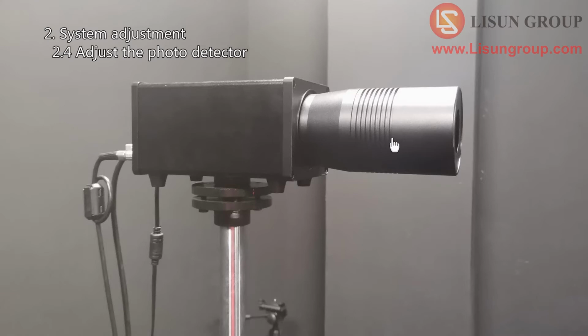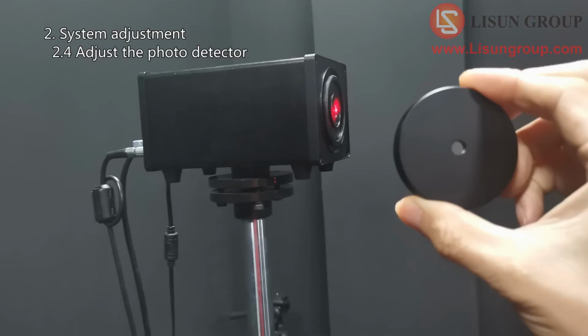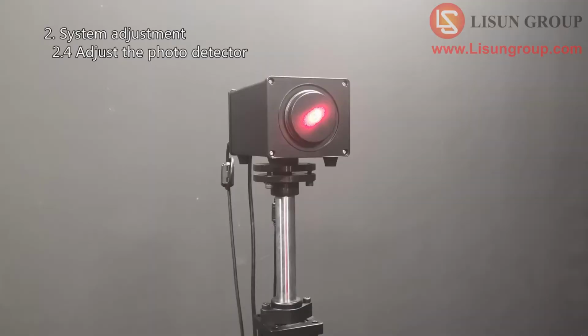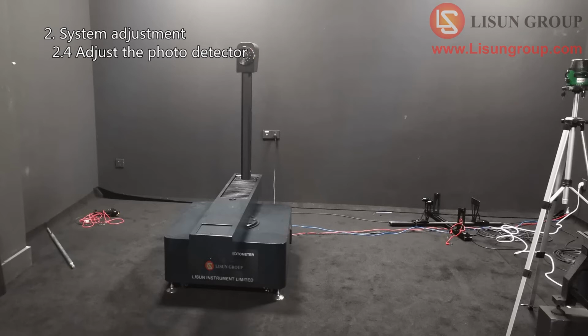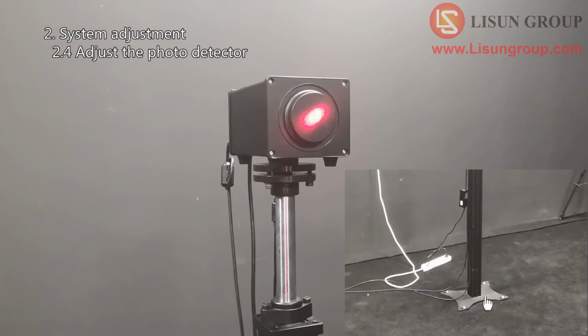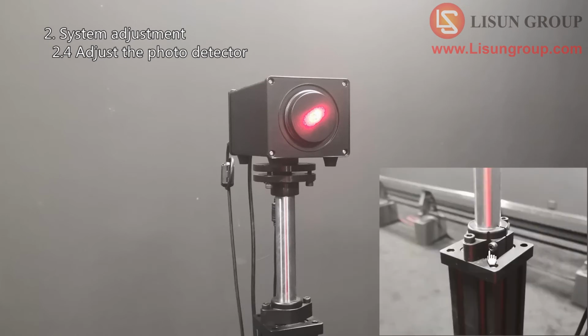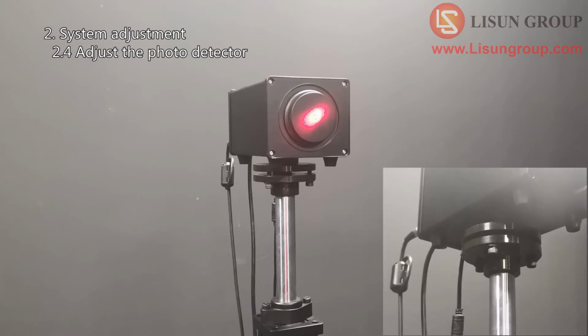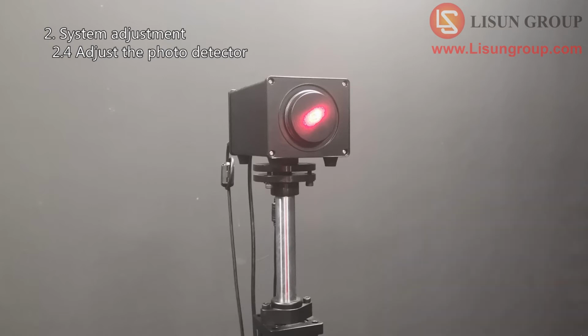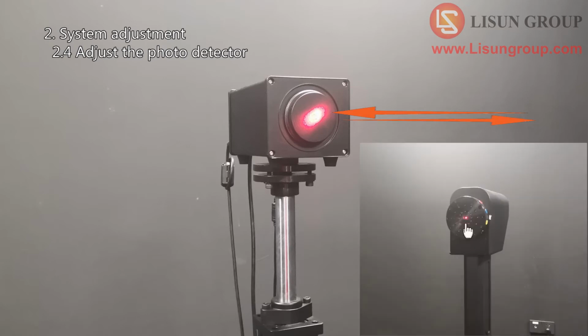Screw down the sleeve of the FAR detector. Install the mirror tool. Now the gamma angle of the goniophotometer is still at 0 degree position. Please adjust the position of the detector holder, the height and direction of the detector. Make sure that the laser from the main arm of the goniophotometer goes to the center of the mirror tool, and the reflected laser goes to its original position. This step also needs patience.